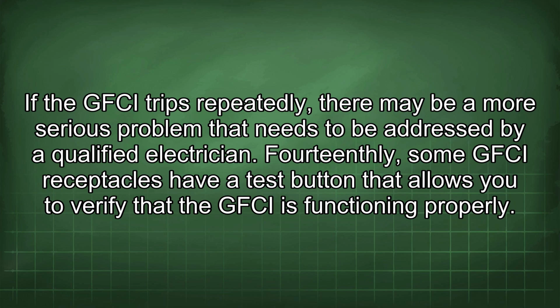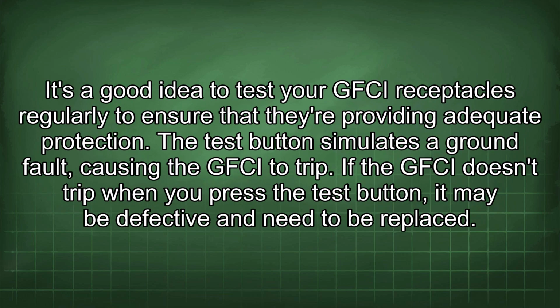14thly, some GFCI receptacles have a test button that allows you to verify that the GFCI is functioning properly. It's a good idea to test your GFCI receptacles regularly to ensure that they're providing adequate protection. The test button simulates a ground fault, causing the GFCI to trip. If the GFCI doesn't trip when you press the test button, it may be defective and need to be replaced.